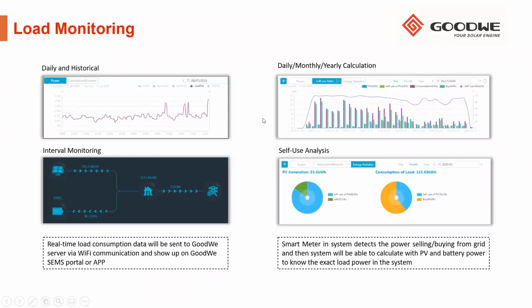So on SEMS portal, we can do a lot of load monitoring. I'll show you a bit more in depth for our fault finding, where we go to see a bit more information. But we just have our general power, our self-use ratio. We'll see the interval load monitoring. So this is a snapshot of every 5 minutes from the inverter itself. So this currently does not update dynamically. So every time you refresh your page, you'll see this will change, but that will be a 5-minute interval snapshot of what was happening on your inverter. Lastly, we also have our energy statistics to see your PV generation versus your load consumption. So should the CT and everything be installed correctly, all your values here will be quite accurate.